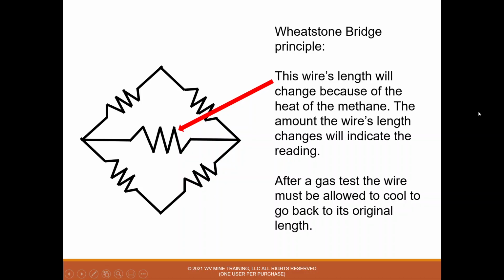I have the electrical diagram of a Wheatstone bridge shown here. Just use your imagination, but the red arrow here is pointing to this wire. So this wire's length will change because of the heat of the methane. The amount the wire's length changes will indicate the reading of methane. So after you take a test, the wire must be allowed to cool to go back to its original length before you take another gas test.